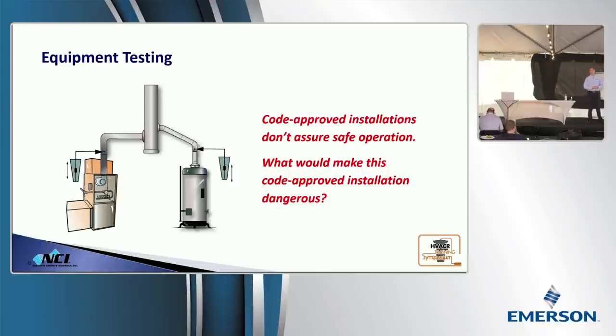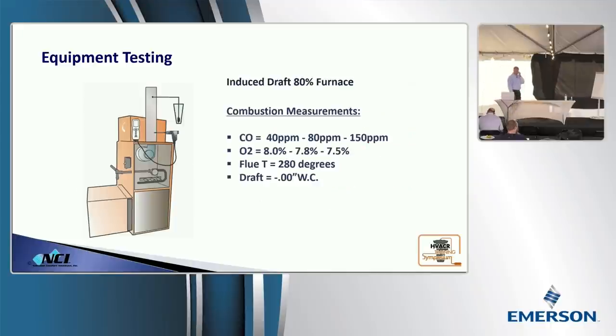And you'll see that through your combustion readings, which we're getting ready to show you. You guys can see this with the draft gauge also, if you're measuring in the flue of that water heater. It will let you know what's going on. Here's the readings. You guys might want to write these down. These readings are indicative of a combustion air problem. And you'll notice we haven't pulled out a tape measure. We haven't looked at anything. All we're looking at are combustion numbers. CO's going up. Oxygen is going down. Temperature's really a non-factor. I'm not too worried about temperature. CO, oxygen, and draft. Where's the draft at? It's like non-existent, isn't it?